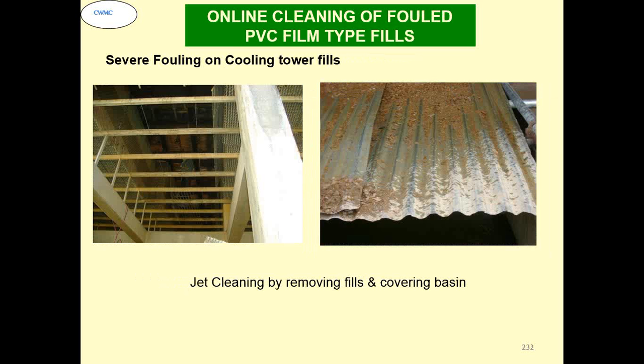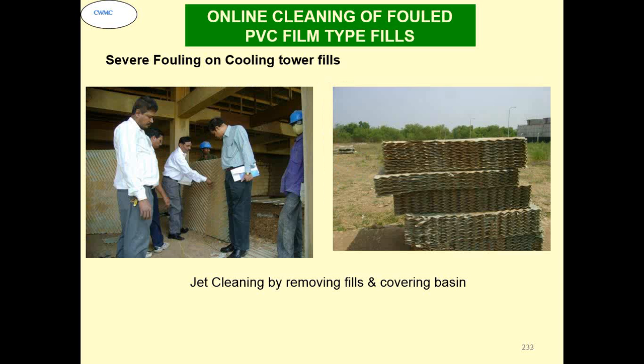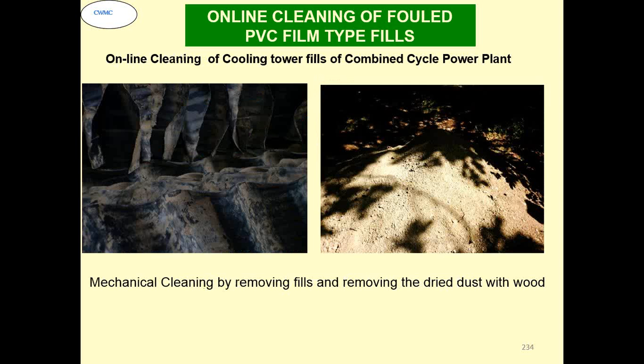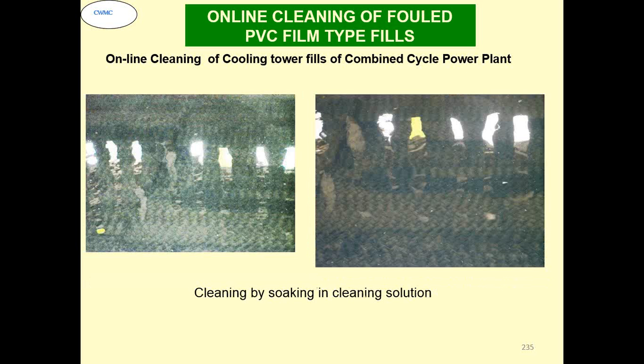We tried high pressure jetting by putting the sheets on the cells. We got some improvement, but not sufficient. This is the kind of fill packs that you see. They are removed and then mechanically cleaned. Normally in mechanical cleaning, people allow the fill packs to dry out, and then they beat them with a wooden piece, so all the dirt goes out. But in that process the fill packs also get damaged because they are made of PVC. They become brittle and break, and after some time you have to replace the fill packs. So this is what was happening.